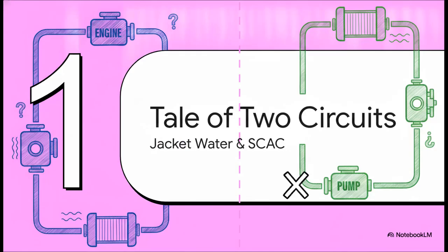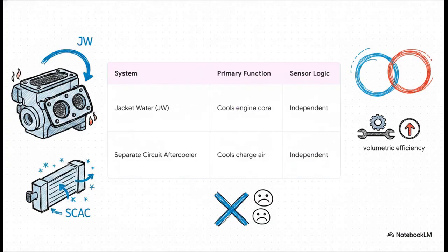Okay, Section 1. The tale of two circuits. To start things off, we literally have to physically separate these two systems in our minds. If you try to treat them as just one big cooling loop, I guarantee it's going to result in wasted diagnostic time. Looking at this breakdown, it's basically our cheat sheet. The jacket water system, or JW, uses a dual-pass design specifically to remove heat from the engine core, so the block and the cylinder head.